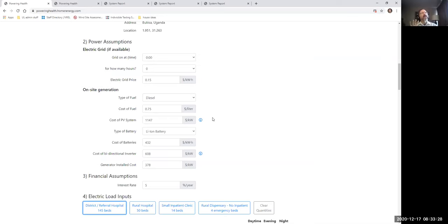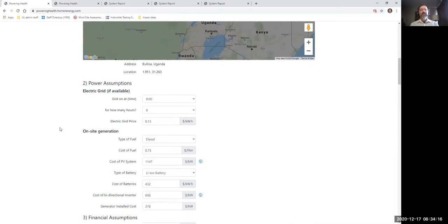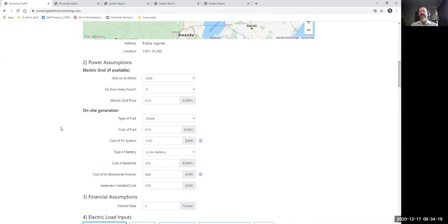And I don't just mean for redundancy purposes. You probably want more than one anyway, because one's on maintenance, but they might be identical and they never run at the same time. But in really large systems, they have multiple generators and they can either parallel with each other or they're different sizes. They're not just for redundancy purposes. So anyway, we have used HOMER to model islands the size of Aruba or Maui or St. Thomas, that's 100 megawatt, 150 megawatt systems, much larger than you'd want for a rural health clinic. In the desktop app, you can have as many generators as you want, but in the web app, we're assuming a single generator. That's the main limitation on size, I think.